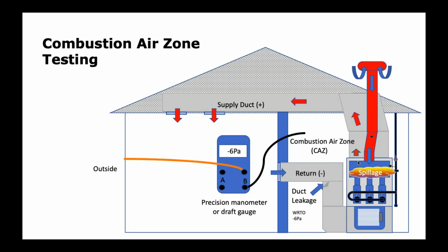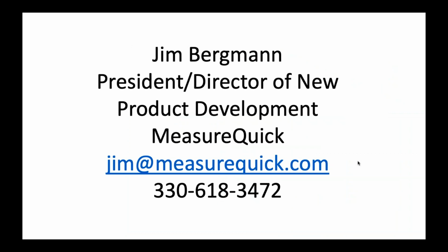And the combustion analyzer has a very high resolution draft gauge we can use to test combustion air zone pressures. A lot of guys use a blower door gauge for this because it has even higher resolution. Combustion air zone testing is a very important part, and that's completely outlined in the combustion guide available from Accutools.